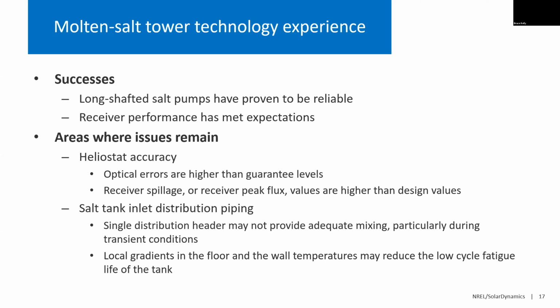The receivers typically met their performance requirements, both in terms of thermal efficiency and other characteristics such as pressure drop, response to transients, and low cycle fatigue life, at least to the extent that these receivers have seen a number of thermal cycles. And so typically, for most of these receivers, they've worked really well. Most of the problems have been in the conventional equipment, primarily in the heliostats, the salt tanks, and the steam generator. On some plants, the heliostat accuracy, which is a warranted value, hasn't really met the requirements. And what happens is the optical errors tend to be higher than what was guaranteed, which has the effect of increasing the receiver spillage because the beams are not really hitting the receiver in the areas that were expected.